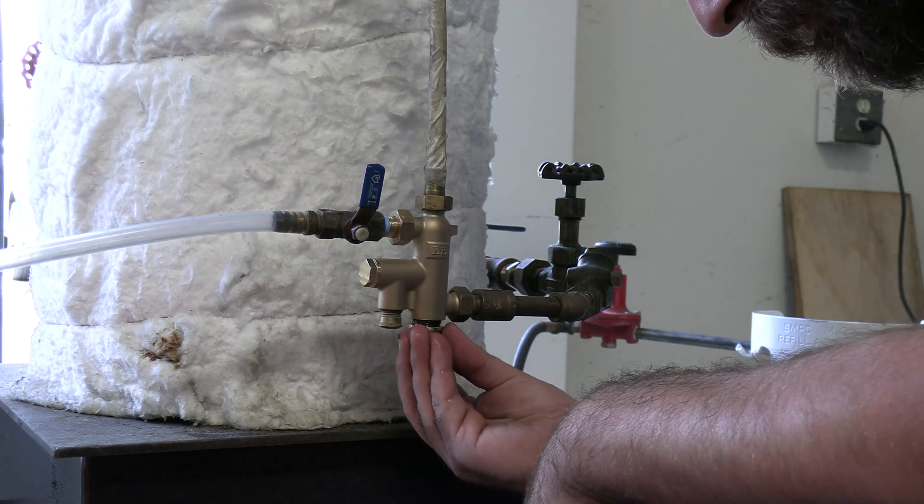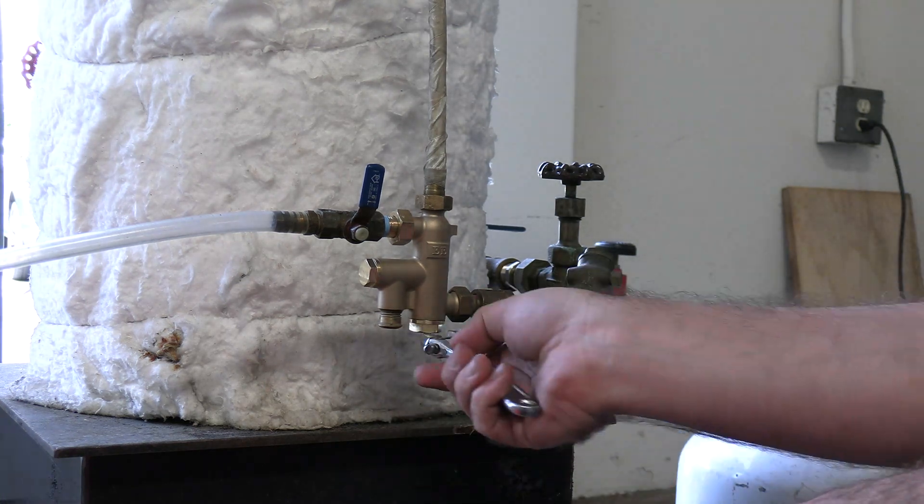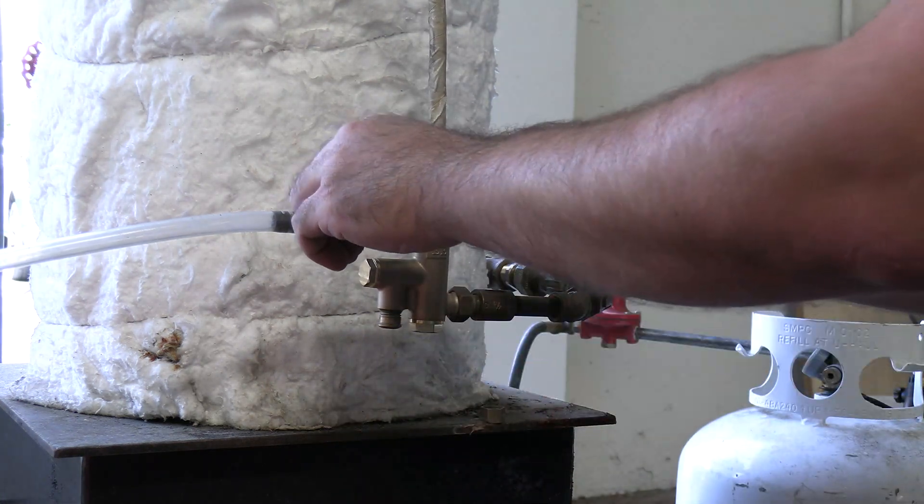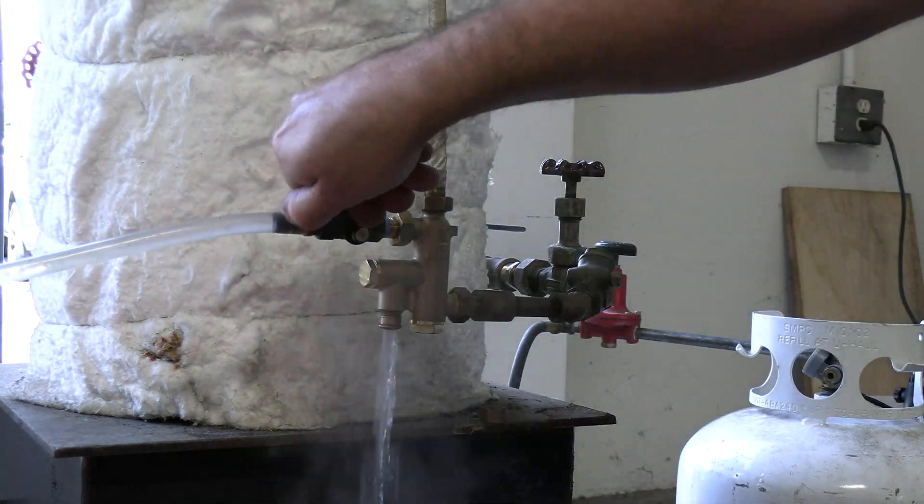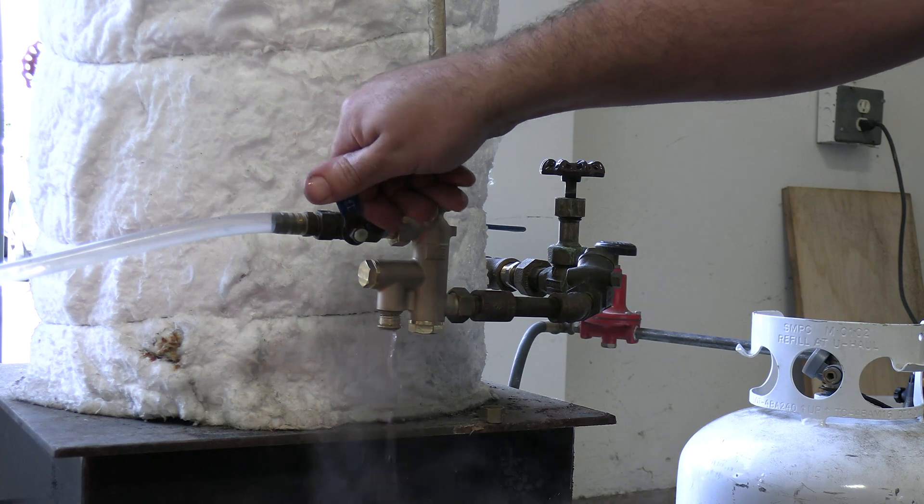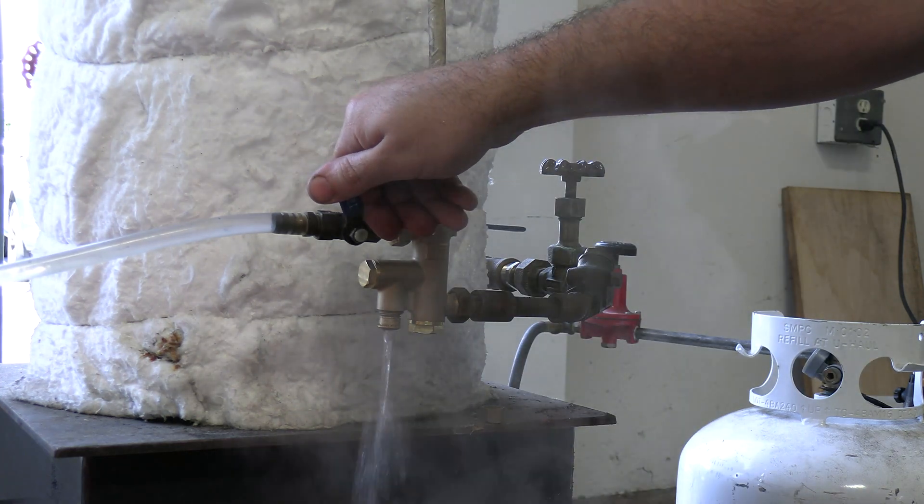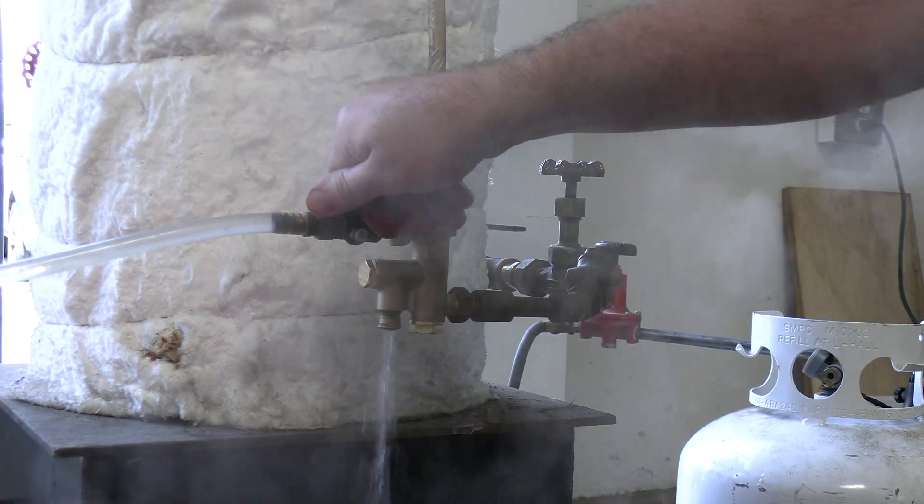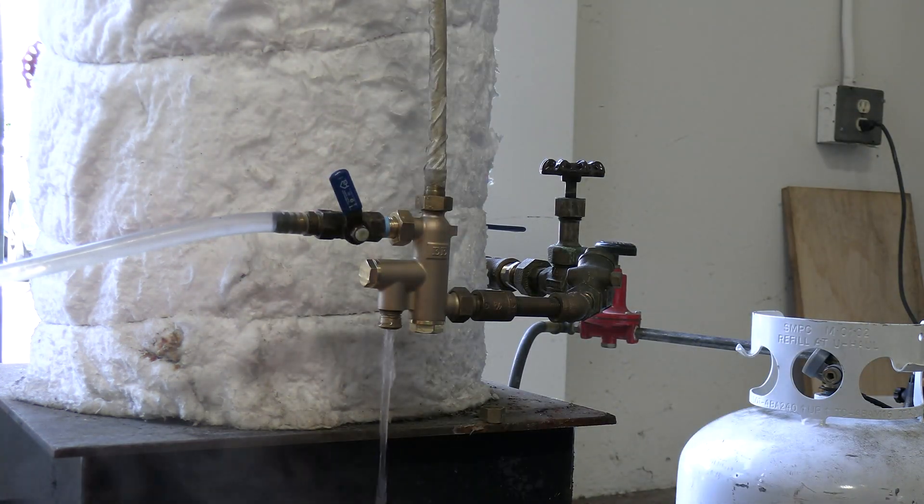Truthfully, it's very hard to distinguish between a stuck washer and an air leak based on the overflow, however the frozen washer will not make that airy gurgling sound. It will sputter steam and water very rapidly, which can look and sound deceptively close to the air leak's gurgle, but it will not pulsate as violently, if at all, when the water valve is restricted. It may occasionally even give you some hope that it wants to pick up.